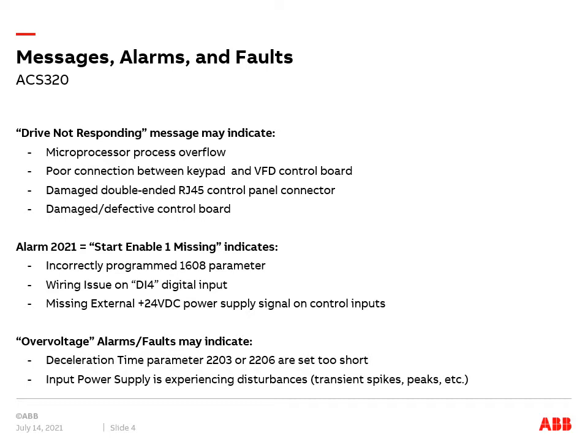When encountered prior to giving the drive a start command, Drive not responding can be an indicator of a potentially damaged or defective drive. The majority of the time, this fault indicates a poor connection between the VFD's control board and control panel.